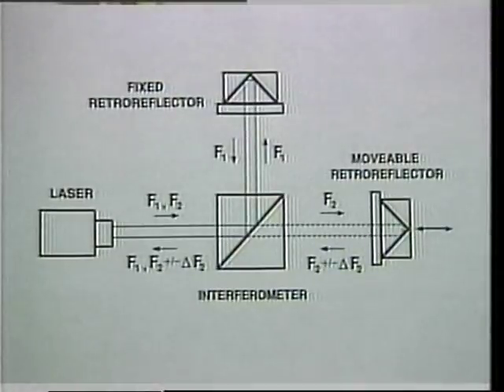In our system here, a helium neon laser produces a beam containing two frequencies of coherent monochromatic light via a process known as Zeeman splitting. These two frequencies have different polarizations and may therefore be separated and recombined through the use of optical components. The separation of the two frequencies occurs at the interferometer's polarizing beam splitter. The reference frequency component, F1, is directed through a fixed path by the stationary retroreflector, while the measurement frequency component, F2, is subjected to the path length variations created by the movement of the measurement retroreflector.